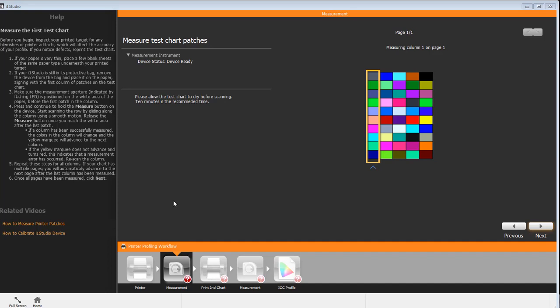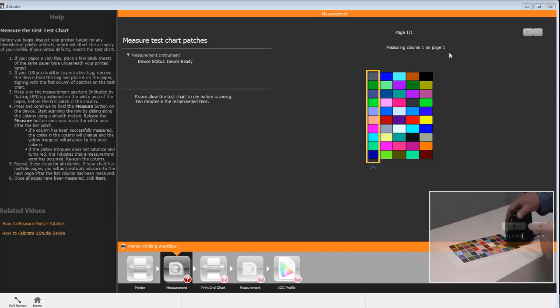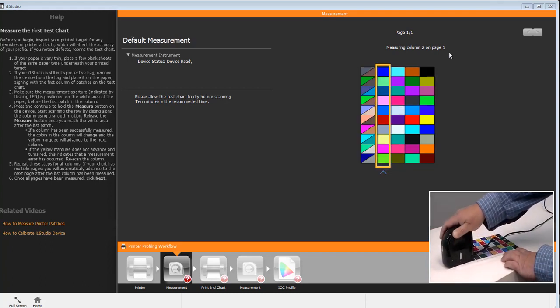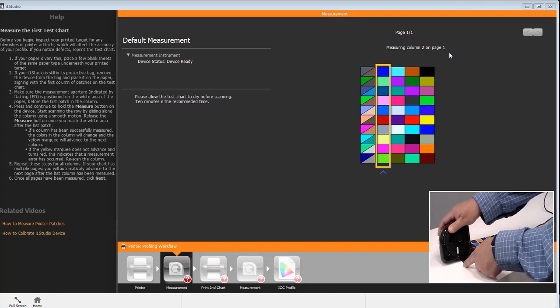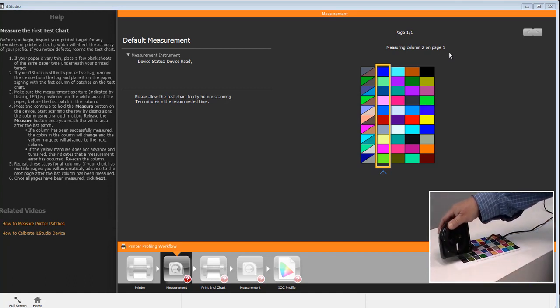Once the device has been calibrated, the software is going to prompt you to begin measurement. As you'll notice, you're going to be measuring page 1 of 1, measuring column 1 on page 1. The software, once again, is going to expect that you're starting at the bottom of the page with the optics of the device on the white of the paper, pressing the button in on the white of the paper. You're going to scroll past all of the patches back onto the white of the paper at the top of the same page, and then you will be prompted to move forward with the yellow marquee.